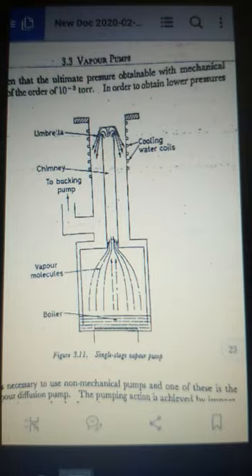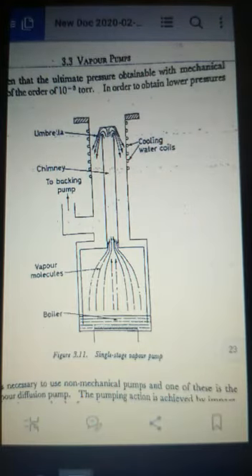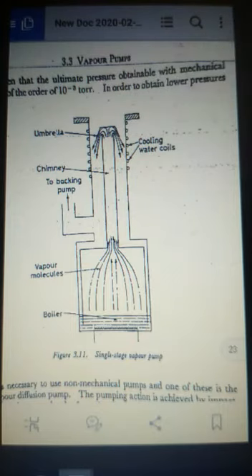The pumping action is achieved by imparting to the gas molecules from the system a momentum in the direction towards the exhaust by means of high speed stream of molecules. The principle and operation is illustrated as shown in the figure. The pump consists essentially of a cylindrical body at base which is a boiler containing suitable fluid. Provision is made for cooling the upper part of the body either by water jets. A chimney projects from the boiler and mounted above the chimney is an umbrella shaped deflector or jet.